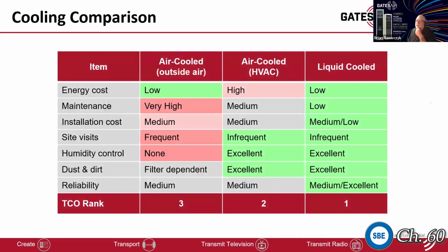So then when you start taking a look at the costs, the energy cost of taking outside air and blowing it into the room is obviously relatively low, versus HVAC, and then of course liquid. Now maintenance can be very high with that for the before mentioned reasons. HVAC has medium maintenance. The liquid cooling is relatively low maintenance.